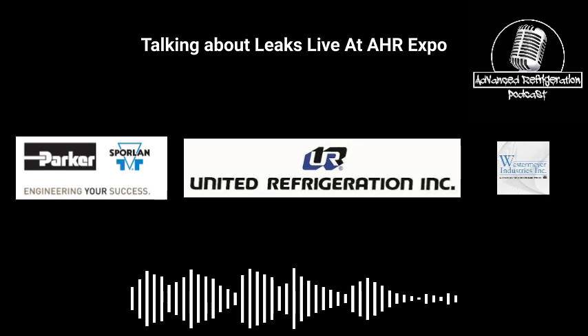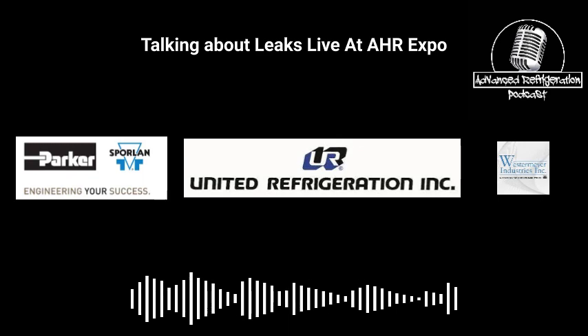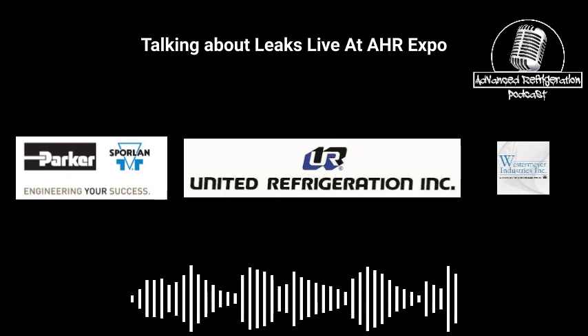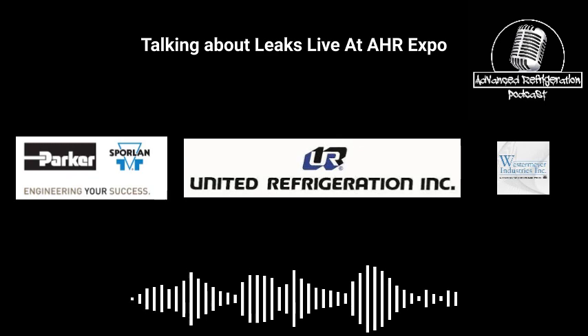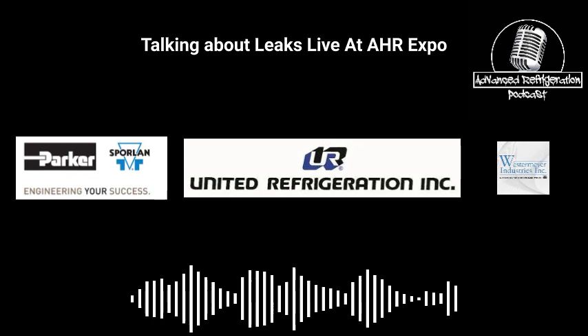So that's one of the things you should be checking as well when you're initially doing all your checks, making sure your valves are open, and tightening those packings back up to make sure that you're not going to get anything through, to make sure that your vacuum goes a lot smoother. So my big thing on the transducer installs is I want them Teflon taped and nylogged, and then I want the packings tightened up, and then I want the caps tightened up, because I don't want to have to go back through and open packed angle valves, or we're doing startup and there's a packed angle valve not open, and then we got something flooding back really hard.